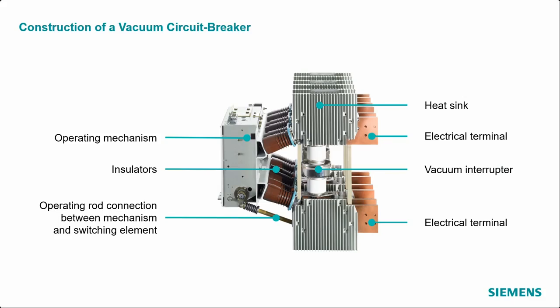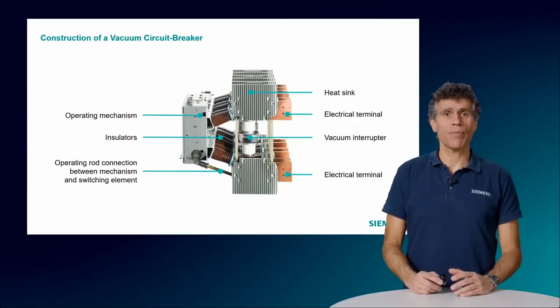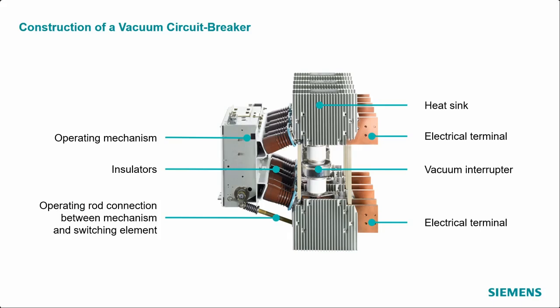The connecting rod facilitates the mechanical connection between the operating mechanism and the switching element. It transmits the forces necessary to open or close the electrical contacts inside the vacuum interrupter. The heat sink parts in a vacuum circuit breaker assist in dissipating the heat generated by the resistance of the copper to the flow of the electrical current, which is particularly high on the touching contacts of the breaker. This is because no bolts are used, but rather only the force provided by the operating mechanism.